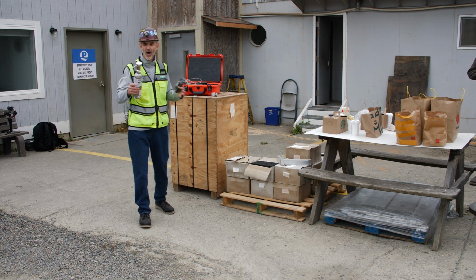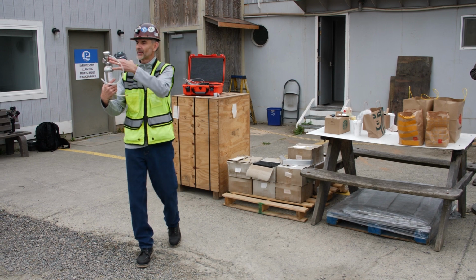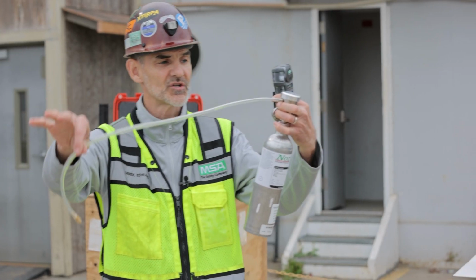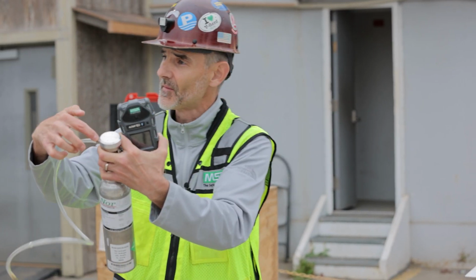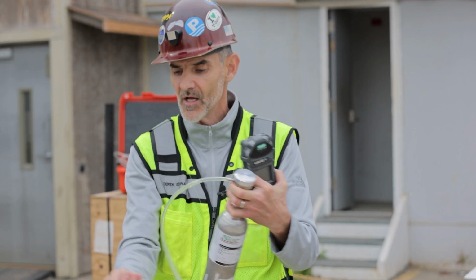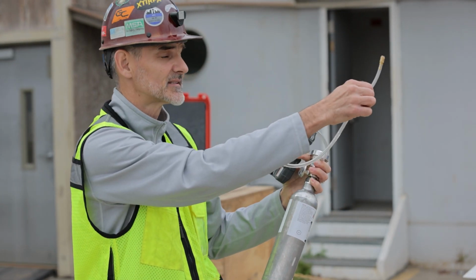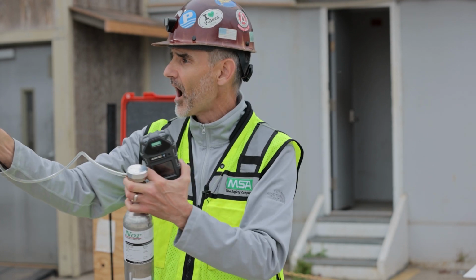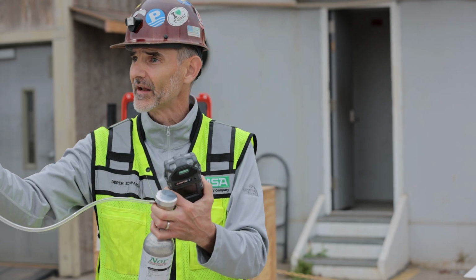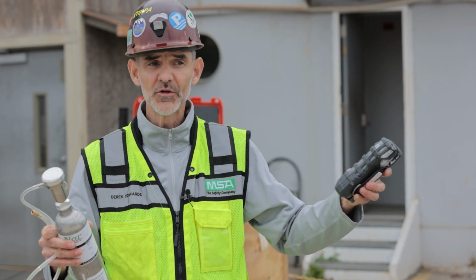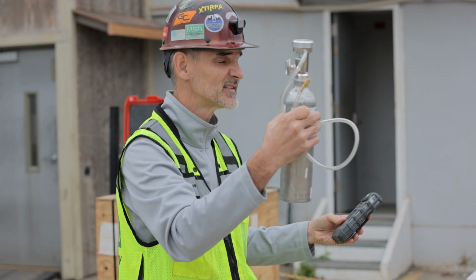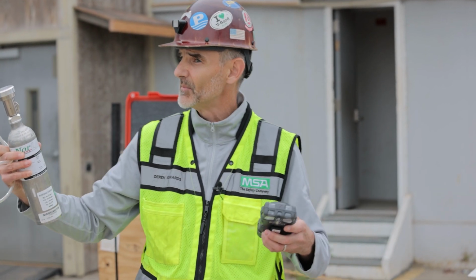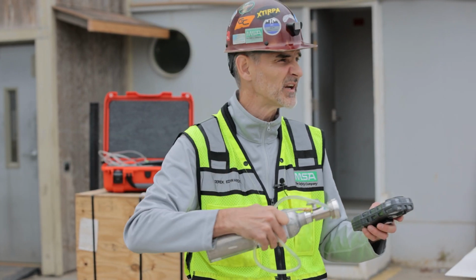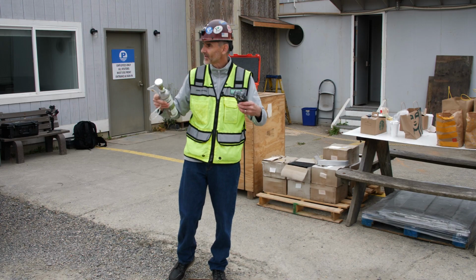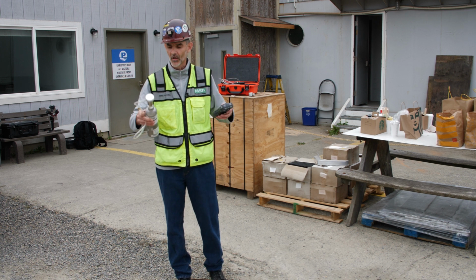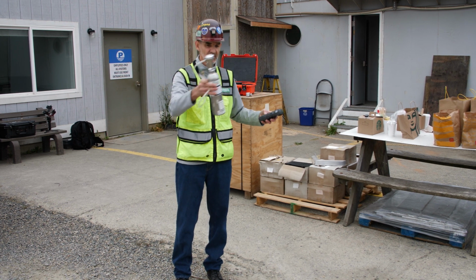So to set up your bottle, you simply screw the regulator on. You're going to have a calibration hose here that may or may not be attached to the bottle. You're going to attach that on there. You'll recognize this is the same connection that we had on our sample line. It's a quick connect fitting, okay? So before we do a bump test, we want to make sure this is all set up just like this, because the instrument will time out when we put it into bump mode. And if you're scrambling to get it all together, it'll time out and you'll have to do it all over again. So get this ready first so you're ready to go.